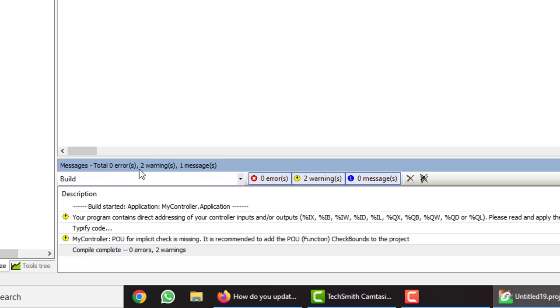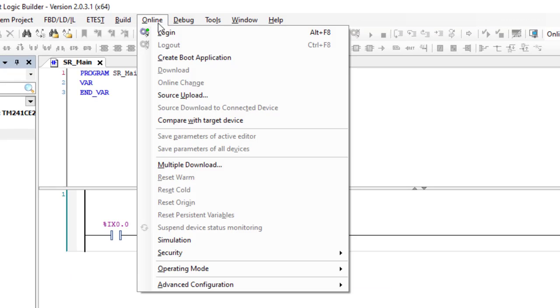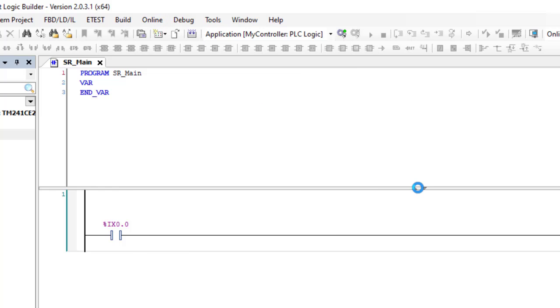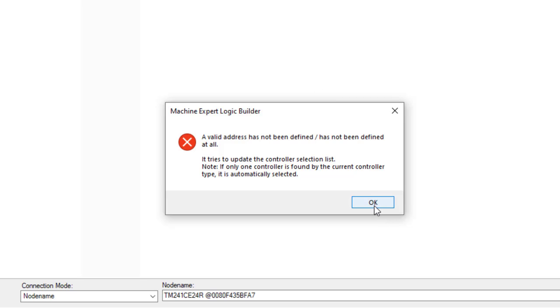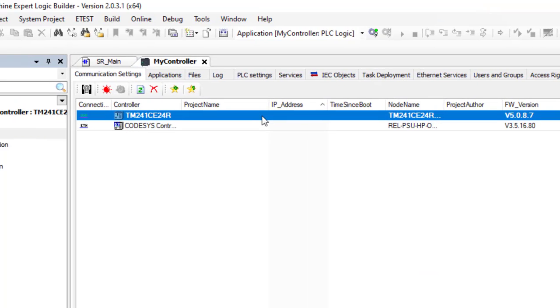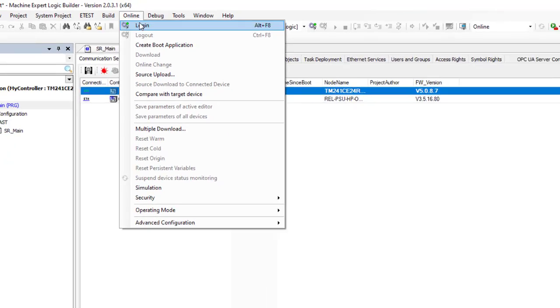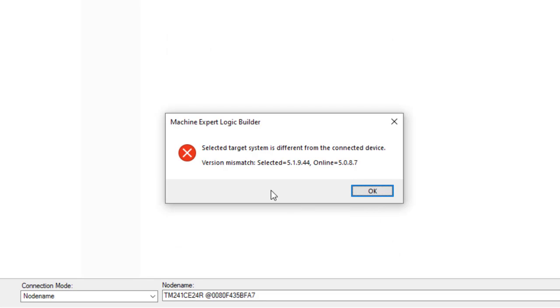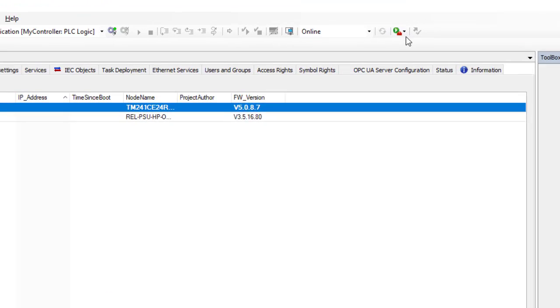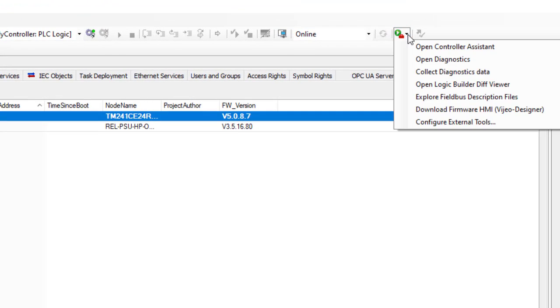Now we can start to log in to the controller in order to download the program. When we press Alt+F8 and try to log in, we get the incompatibility issue — the firmware version in the software is different from the firmware version in the PLC. To solve this, we go to the Controller Assistant and choose the first option: 'Open Controller Assistant'.